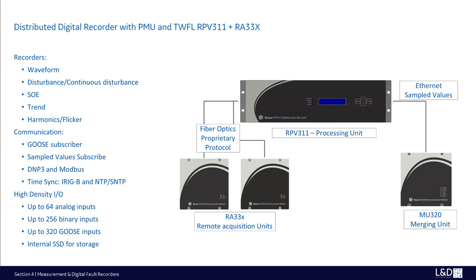RPV311 can be synchronized with IRIG-B and NTP or SNTP. IRIG-B is mandatory for the PMU and TWFL. NTP, SNTP are only for fault recording and other non-time critical features. With up to 64 analog, 256 digital inputs and up to 320 GOOSE inputs per processing unit, the whole plant or substation information can be saved into one single device. With over 30 GB of solid-state internal memory, the RPV311 can keep the data for years without the need for external storage devices.